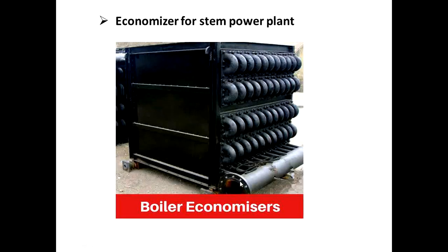Now let me explain the applications of the fins. Fins for the economizer of a steam power plant. Here, the burnt air-fuel mixture, that is the exhaust gas, will pass through this particular point. While it is passing here, it exchanges heat energy to the water which is coming to the boiler. Then the water will warm up and absorb the sensible heat.